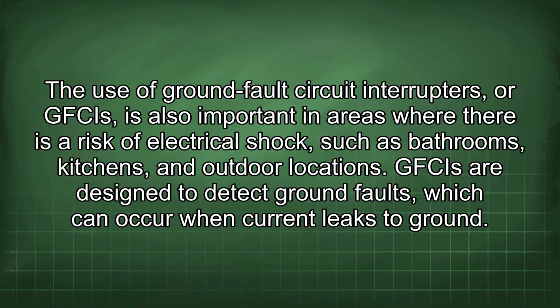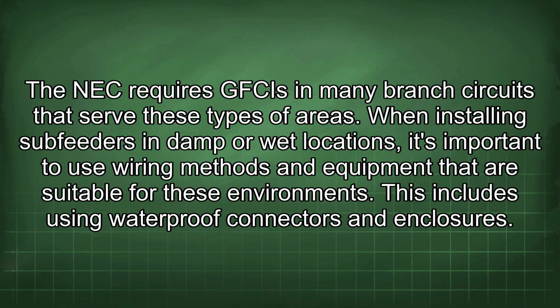The use of ground fault circuit interrupters, or GFCIs, is also important in areas where there is a risk of electrical shock, such as bathrooms, kitchens, and outdoor locations. GFCIs are designed to detect ground faults, which can occur when current leaks to ground. The NEC requires GFCIs in many branch circuits that serve these types of areas.